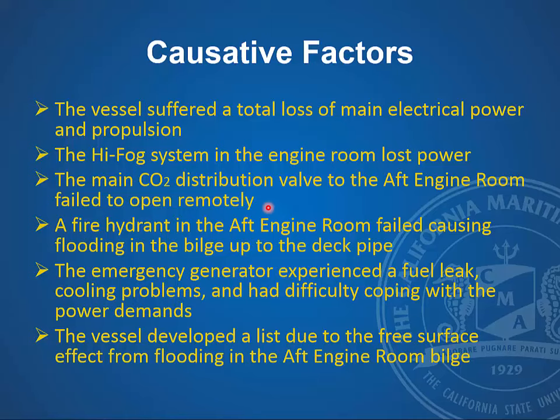There was a problem with their CO2 distribution valve, so they had to manually go down and dump CO2 into the engine room. They couldn't do it remotely. They had a fire hydrant fail, causing flooding. The diaphragm blew out on it, and it caused flooding in the engine room. The emergency generator experienced a fuel leak, cooling problems, and had difficulty coping with the power demands. So not only did they lose all their generation capacity in the engine room, when their emergency diesel generator was operated for a long period of time, they found that it had different problems and they were having difficulty keeping power onto the emergency board.